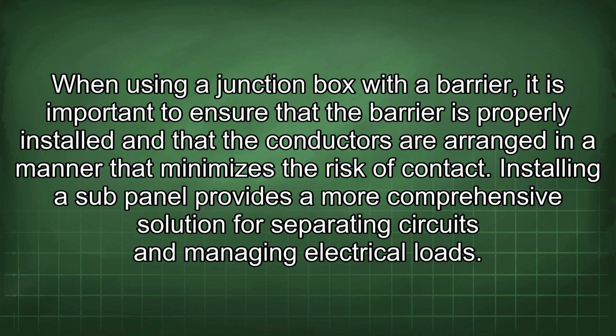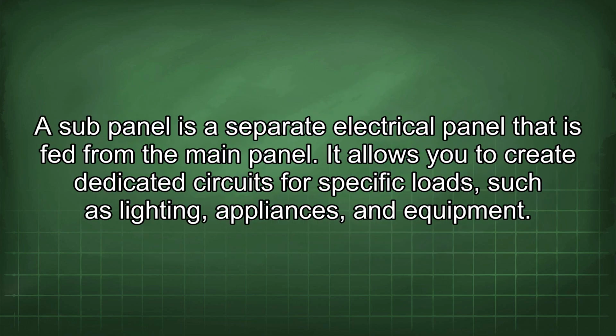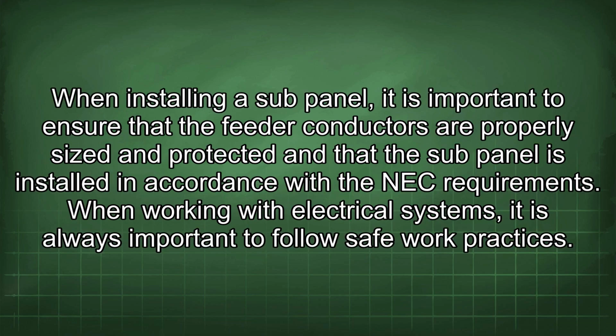Installing a sub-panel provides a more comprehensive solution for separating circuits and managing electrical loads. A sub-panel is a separate electrical panel that is fed from the main panel. It allows you to create dedicated circuits for specific loads, such as lighting, appliances, and equipment. When installing a sub-panel, it is important to ensure that the feeder conductors are properly sized and protected and that the sub-panel is installed in accordance with the NEC requirements.